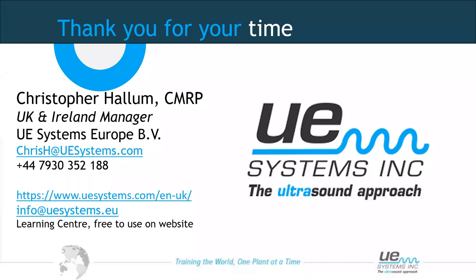On how to start using this technology with no existing limits for ultrasound levels: start with training — understand what you're listening to, gain your baselines, understand what you're listening for. Then it's about trending: collect your first level and trend it over time. If you already have a bad bearing, the next reading will show increased sound that keeps rising over time. A good bearing will stay at that level for a prolonged period.